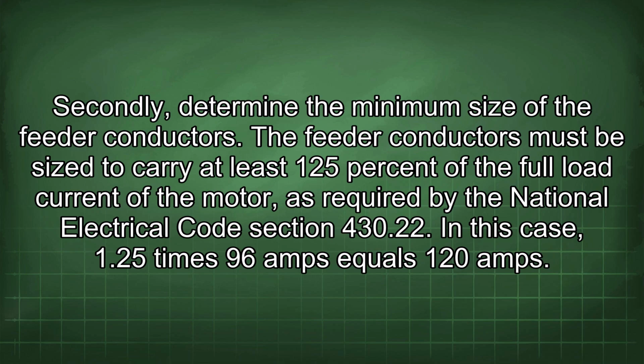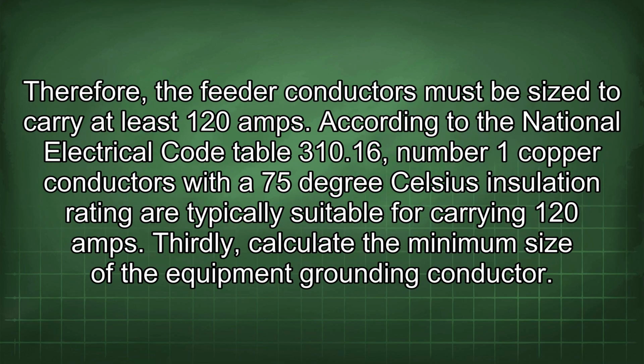Secondly, determine the minimum size of the feeder conductors. The feeder conductors must be sized to carry at least 125% of the full load current of the motor, as required by the National Electrical Code Section 430.22. In this case, 1.25 times 96 amps equals 120 amps. Therefore, the feeder conductors must be sized to carry at least 120 amps. According to the National Electrical Code Table 310.16, number 1 copper conductors with a 75°C insulation rating are typically suitable for carrying 120 amps.